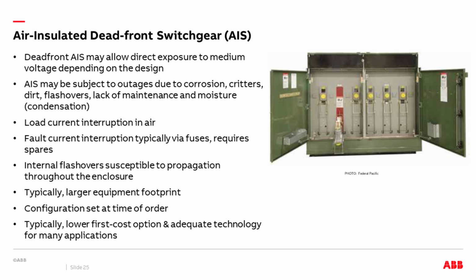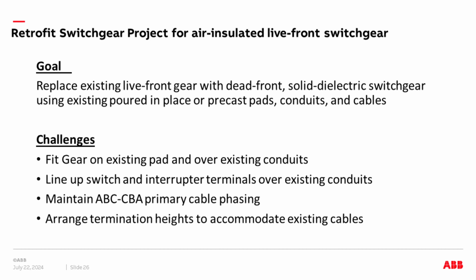There's also a dead front version of air-insulated switchgear. Here's a picture where there's a panel in front of the live front component, so that when you open the door, you're not facing exposed bus and terminations. There are also some mechanical handle mechanisms here that allow you to open up the fuse connection, pull that out, and replace it all with hot sticks.